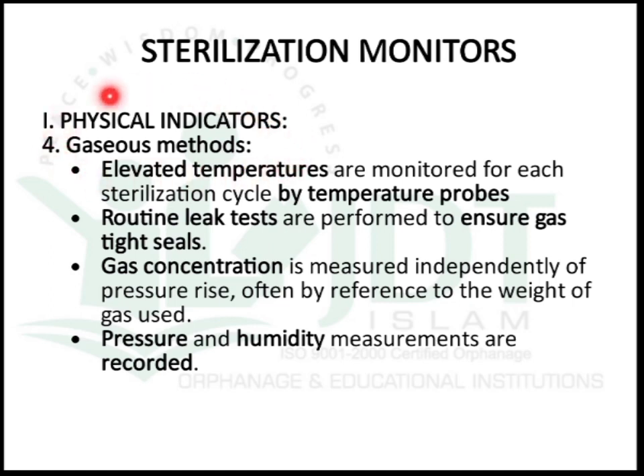For physical indicators in gaseous sterilization, elevated temperature is monitored in each sterilization cycle by temperature probes. At regular intervals, routine leak tests are performed to ensure a gas-tight seal. Gas concentration is measured independently, often referenced against the weight of gas used, and pressure and humidity measurements are recorded at regular intervals.